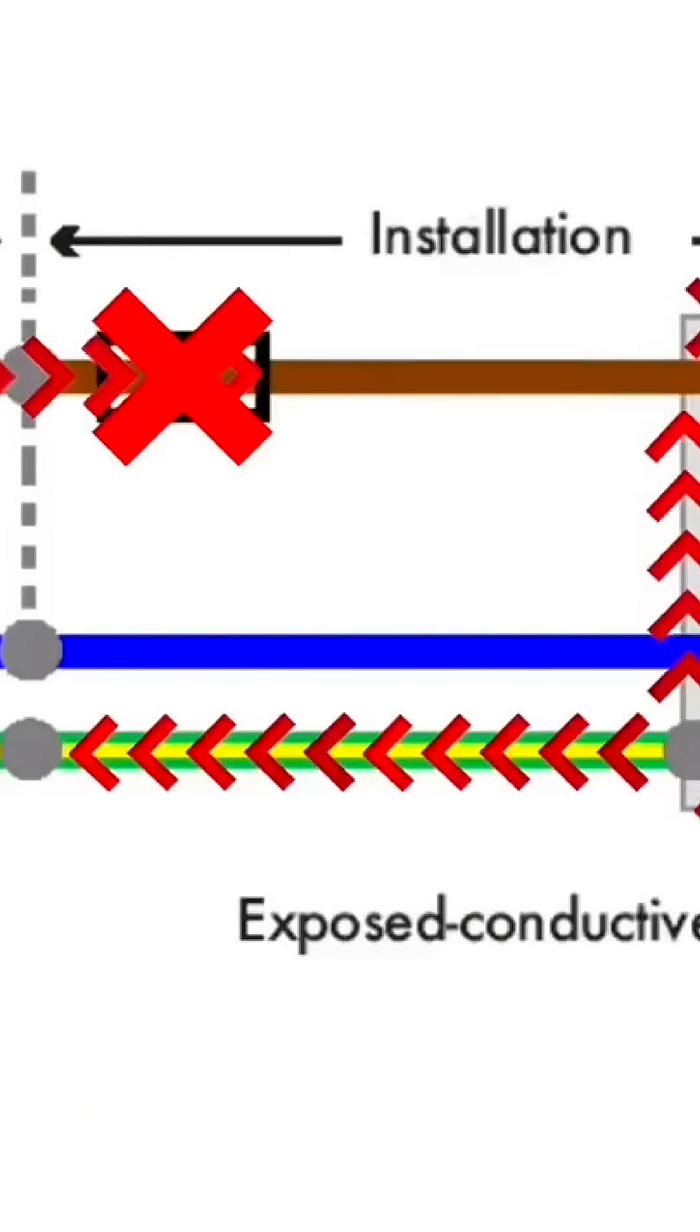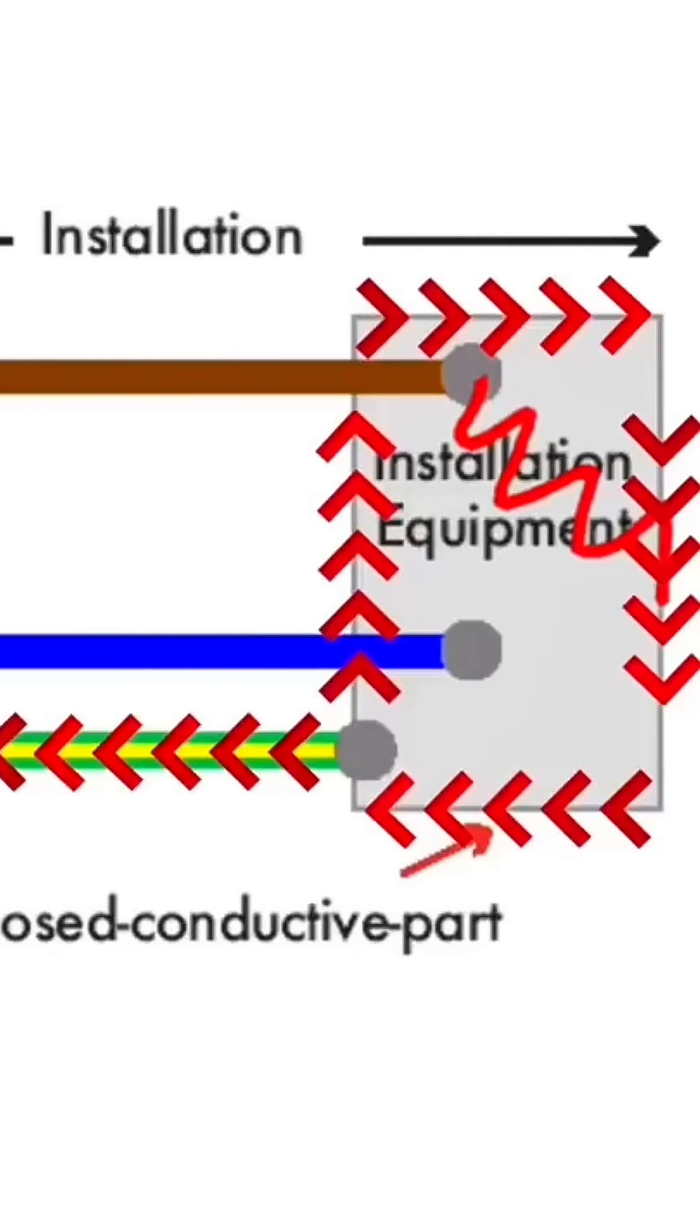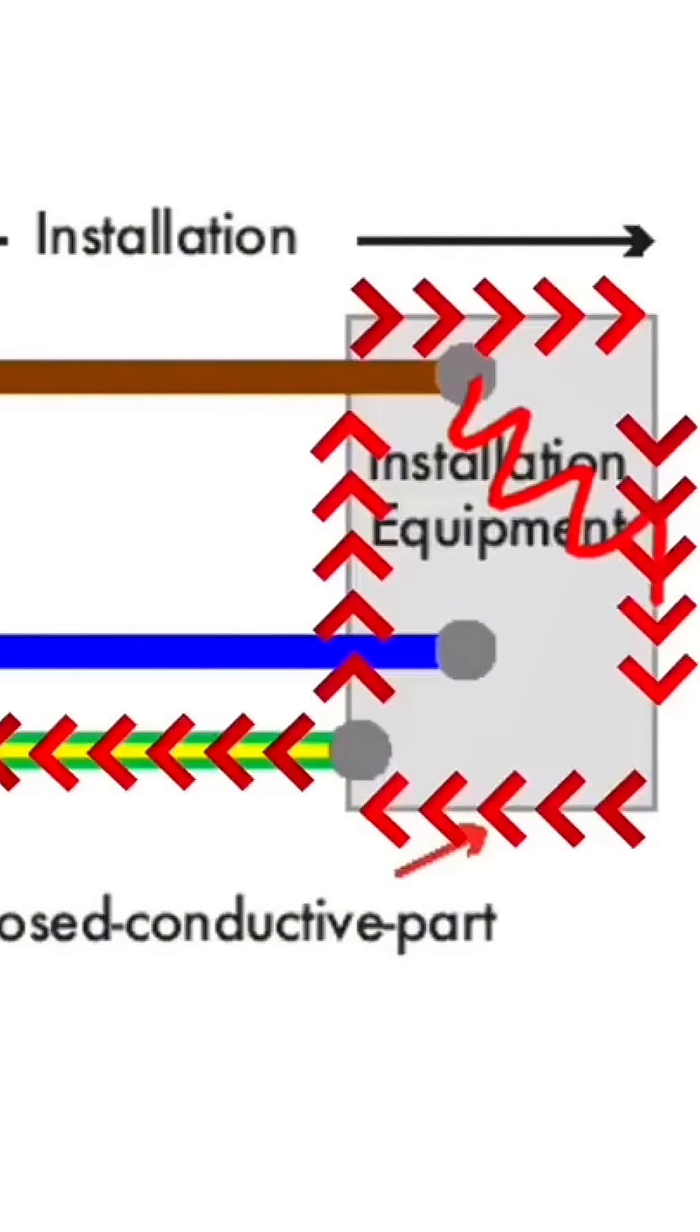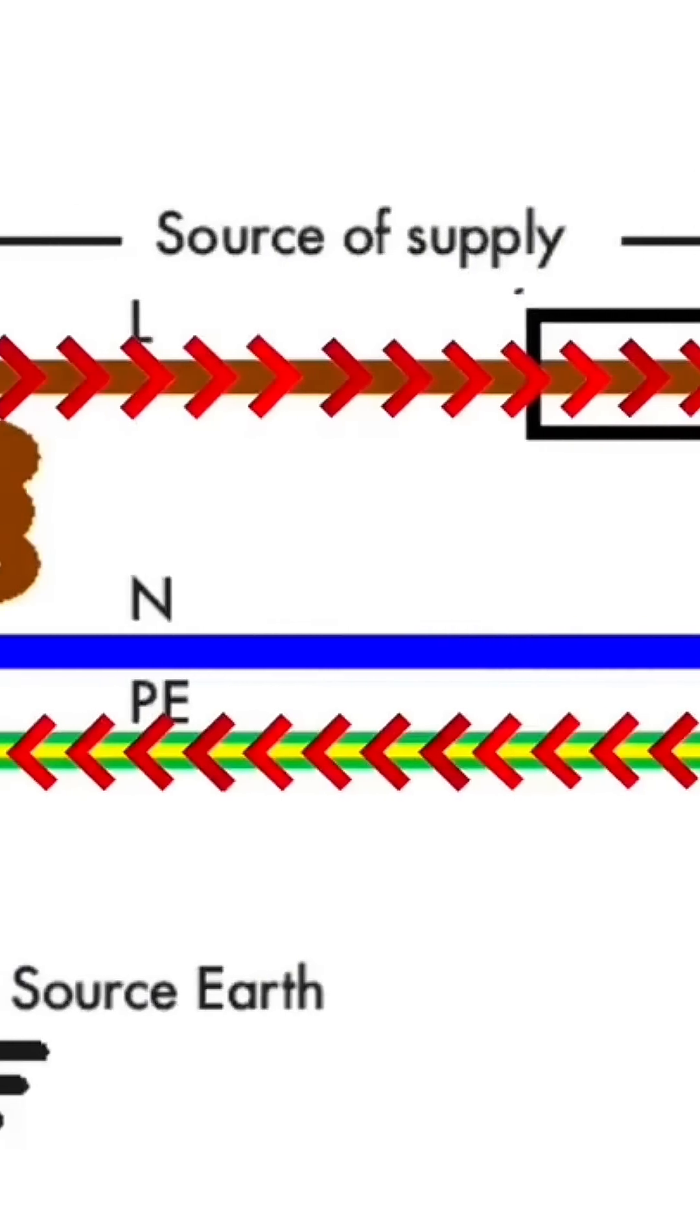This is the full earth fault loop path and needs to be a very low impedance in order to generate a very high fault current to cause rapid operation of the overcurrent protection device.